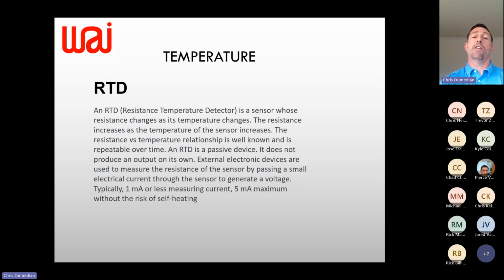So with that output, most people will buy what looks like a puck that they put in their enclosure, and that puck can be a couple hundred dollars. It needs to interpret that resistance value and give you your 4 to 20 milliamp or 0 to 10 volt or whatever your signal output is. They're big, they're bulky, they're expensive, and that's how people have done it for I don't know how many decades. And you'll see down here, it generates a voltage, one milliamp or less measuring current. So it's a very low level signal.